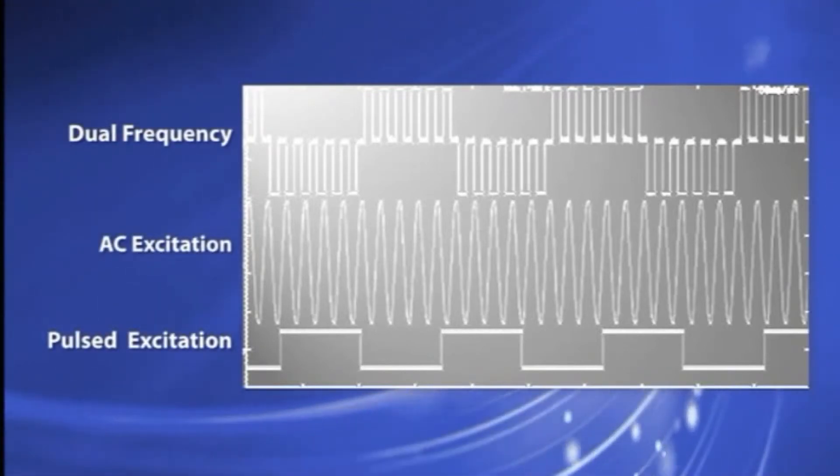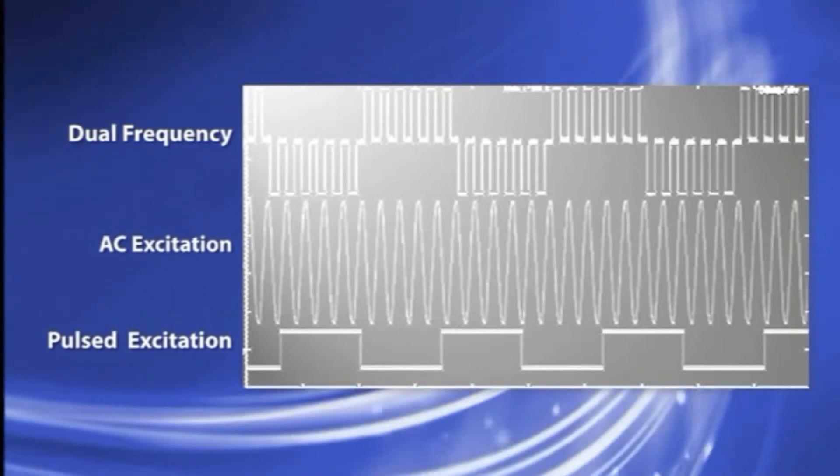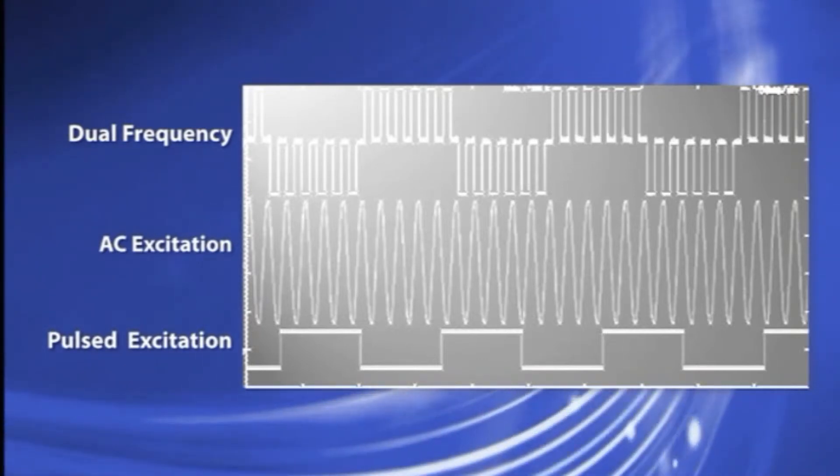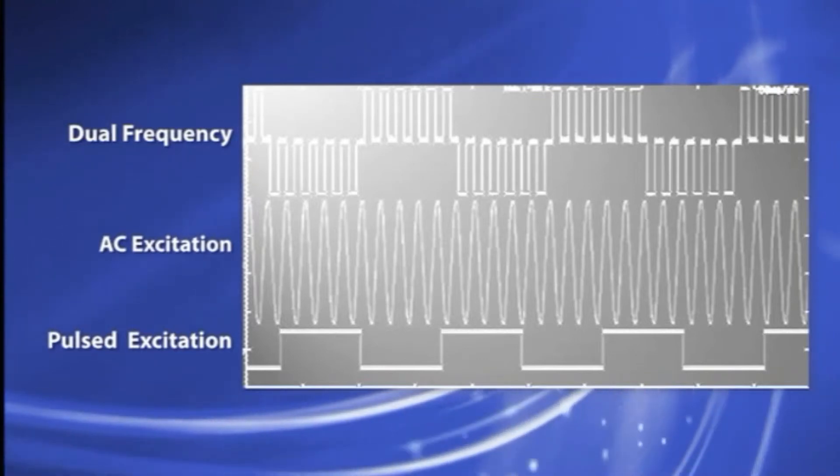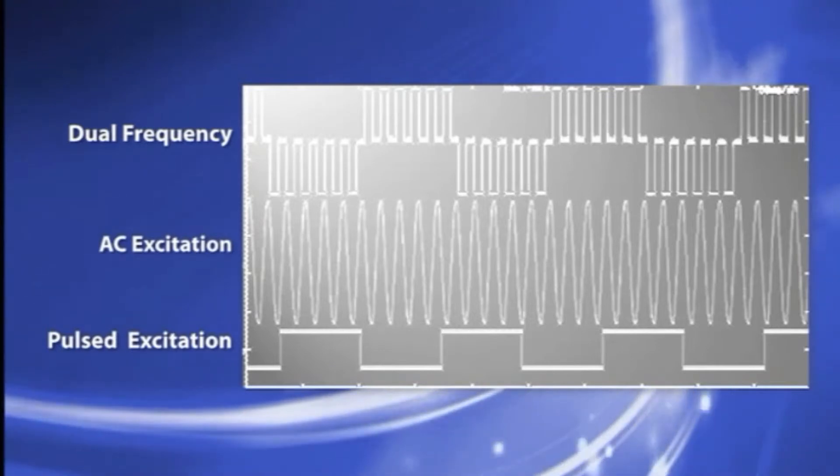Dual frequency excitation combines the positive benefits of both AC and DC excitation, using both a high 75 hertz frequency and a low frequency excitation of approximately 6 hertz to drive the coils.